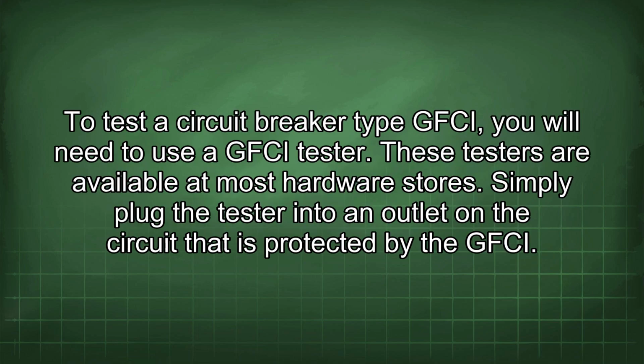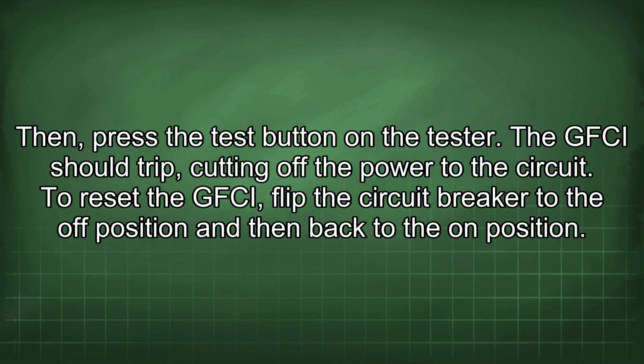To test a circuit breaker-type GFCI, you will need to use a GFCI tester. These testers are available at most hardware stores. Simply plug the tester into an outlet in the circuit that is protected by the GFCI. Then press the test button on the tester. The GFCI should trip, cutting off the power to the circuit. To reset the GFCI, flip the circuit breaker to the off position and then back to the on position.